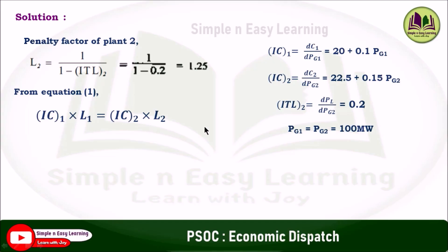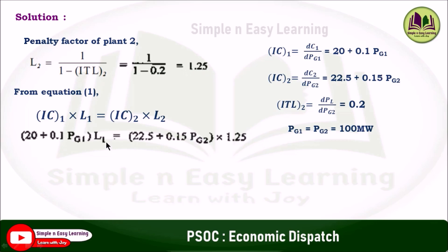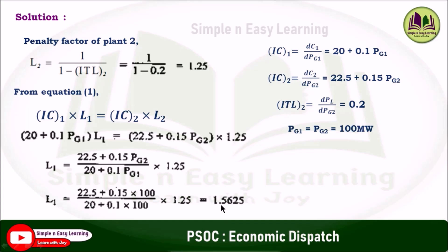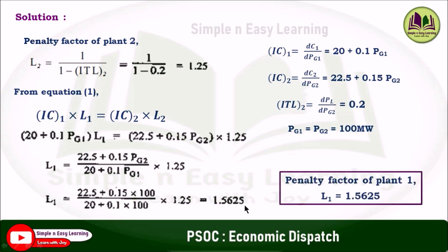IC1 and IC2 are given in the problem, and L2 = 1.25 from the previous step. The only unknown is L1. Substituting PG1 = PG2 = 100 MW into the incremental cost expressions and simplifying — bringing (20 + 0.1·PG1) to the denominator on the right-hand side — yields L1 = 1.5625. Therefore, the penalty factor of plant 1, L1, is equal to 1.5625.